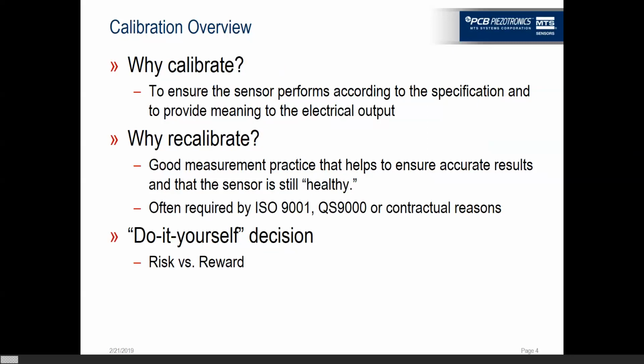It's often required that you do recalibrations for your systems by either ISO 9000 or contractual reasons or some other quality system that you may be working with. And at the end of the day, the decision of not only why you should recalibrate, but how often, is a risk versus reward thing. If you take 3 months worth of data, 3 years worth of data, and you don't do a recalibration or a calibration check, and somebody calls into question your data to show, hey, this isn't the actual correct value that you measured here, what does that mean for the quality of all your measurements since your last calibration? So calibration and your calibration interval are definitely a risk versus reward thing.